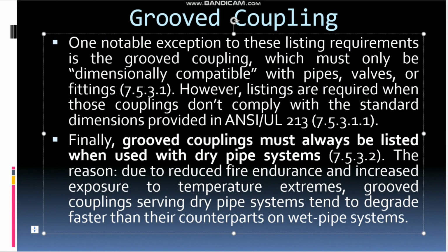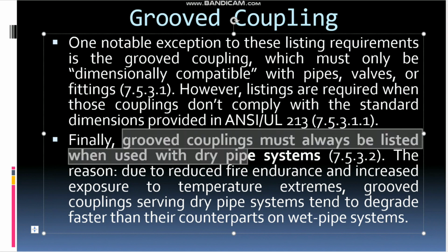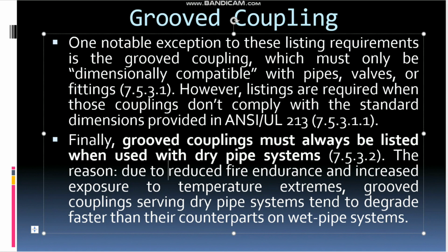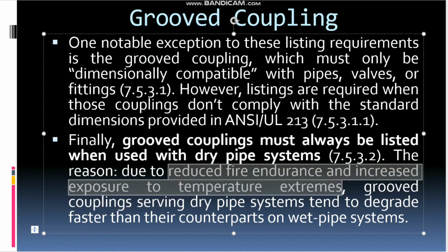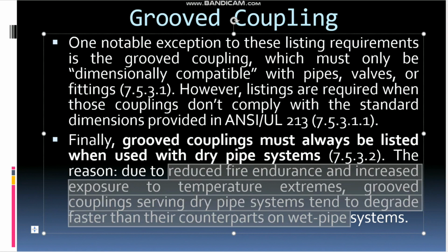It should be only dimensionally compatible with the pipes, valves or fittings. However, listings are required when those couplings don't comply with the standard dimension. So they are talking about the dimension only; the dimension should comply with the pipes, fittings or valves. Finally, grooved couplings must always be listed when used with a dry pipe system. So only for the dry pipe system do we have to have the listed one; for other systems like the wet system we don't need listed grooved couplings. The reason is that, due to reduced fire endurance and increased exposure to temperature extremes, grooved couplings serving dry pipe systems tend to degrade faster than their counterparts in wet pipe systems. So this is the important thing.